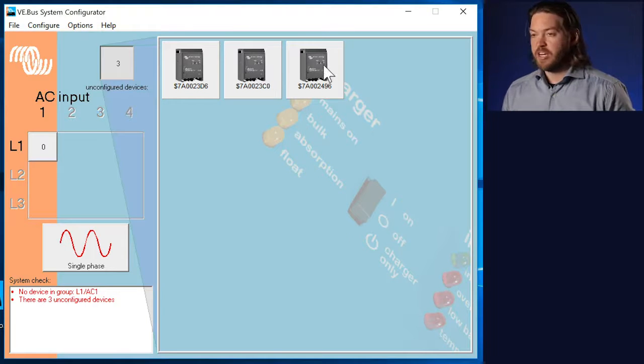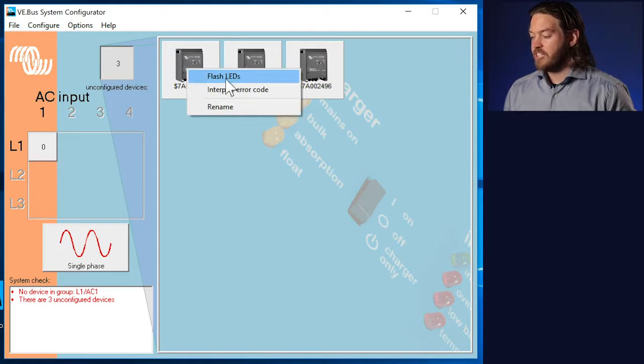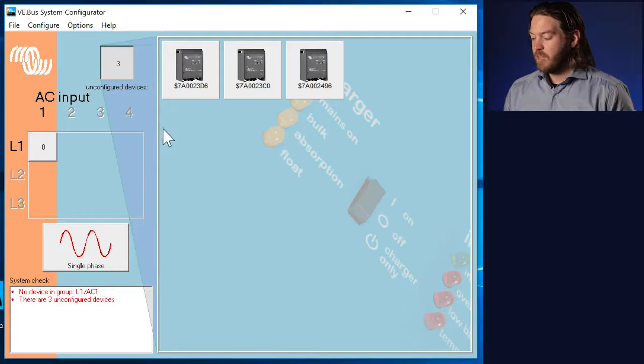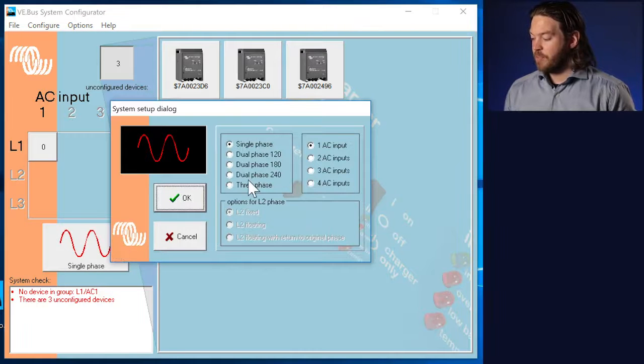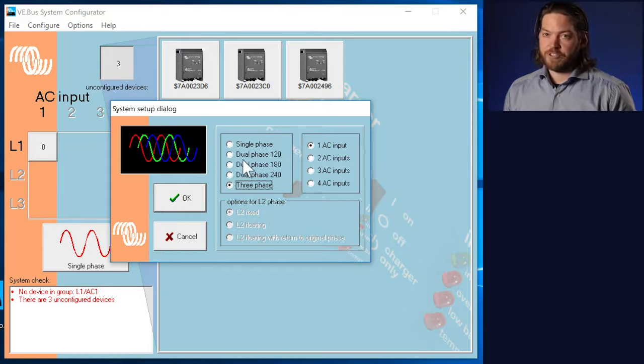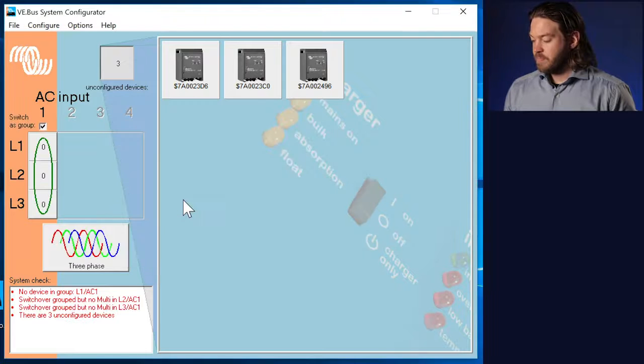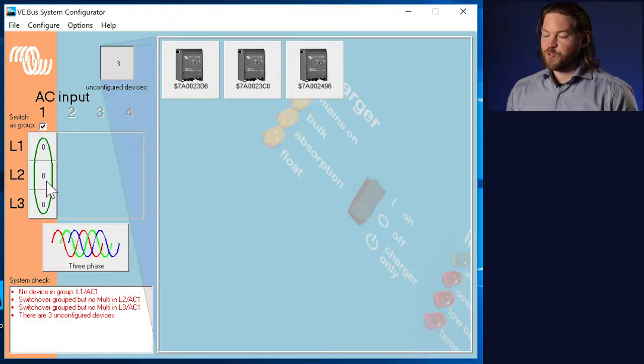Now the 3 units are going to be presented in a relatively random order. To find the right one, we can right click and select flash LEDs, and I'll show you more about that in a second. The first thing we're going to do though is head down here where it says single phase as a default, click that button, and then we can select 3 phase as an option. There are other options here as well for different configurations. We won't go into those right now. I also want to keep 1 AC input selected. We now have 3 buckets we can put these Multi+2s into.